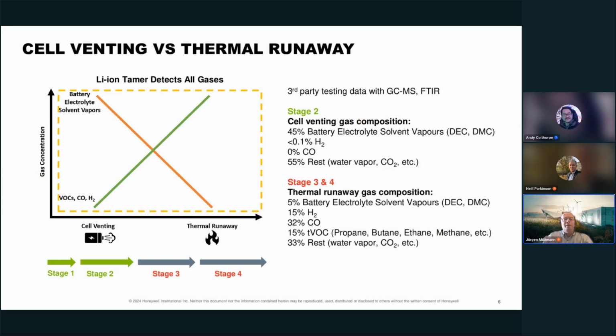So why is the Li-ion Tamer, that's the name of the product we have in our portfolio, able to detect as early as we see here? It's looking at the cell venting, and this is around half of the composition of the electrolyte solvent vapor. During the stage up to the thermal runaway, its concentration decreases and the other components increase. This is the reason why the common technology only detects close to the point of the thermal runaway. The Li-ion Tamer is specially designed for detecting electrolyte solvent vapor, so a much earlier stage.